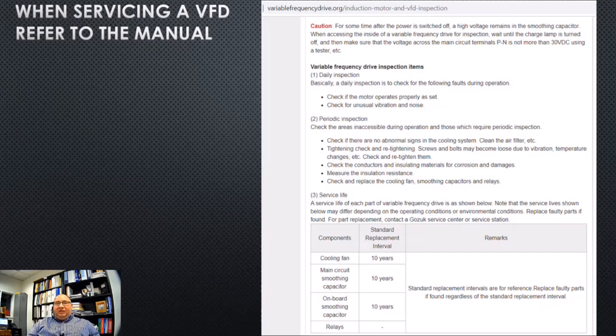When accessing inside the variable frequency drive for inspection, wait until the charge lamp is turned off, and we make sure the voltage across the main circuit terminals P and N is not more than 30 volts DC. Now, that's something to remember. That's DC. Remember, this is the DC bus. Some VFD drives have a little light in there that when the power goes out, you actually will see that light dim and then fully go out. And what that's doing is it's telling you the status of the DC bus.